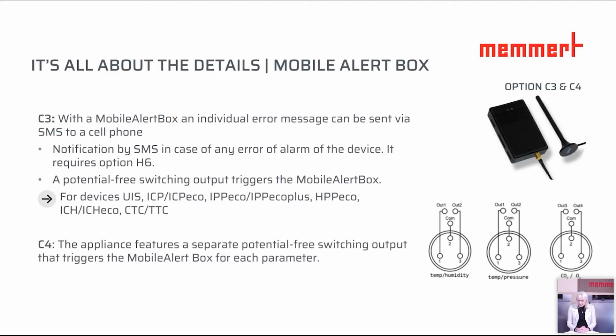Here we have then the temperature and pressure for giving the alarms. And furthermore, we have the possibility for the ICO. ICO means, for example, depending on the accessory of the CO2 incubator, if it's equipped with the T6 option, which refers to the oxygen supply, then we also have the outlets 3 and 4, which refer to CO2 and O2 error messages, along with the output in regard to the temperature and humidity. So that means at the rear of the unit, these two potential free switching outputs would be installed. Let's go on to the next option.